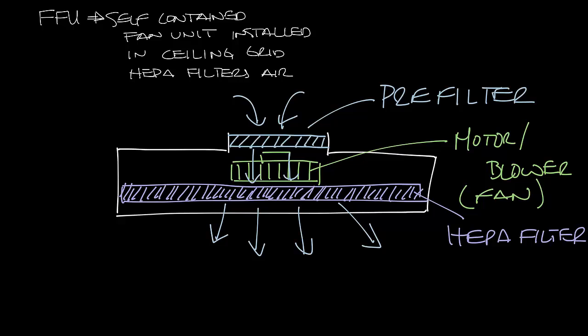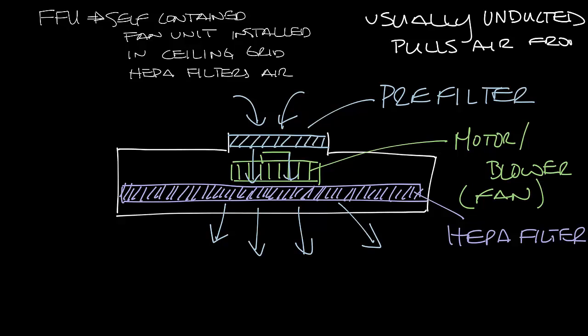You can get an inlet that you can duct to on a fan filter unit but often they are unducted and they just pull air from the ceiling plenum. So an air handler would put conditioned air into the ceiling plenum and then the fan filter unit would pull it out and filter it before it goes to the space.